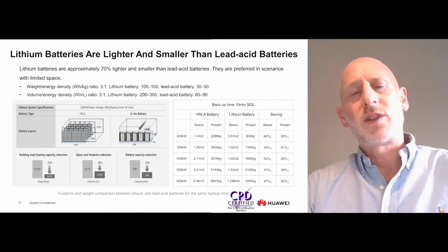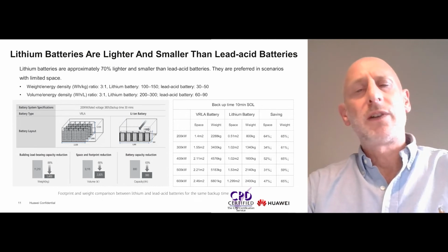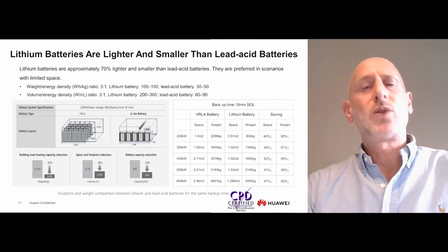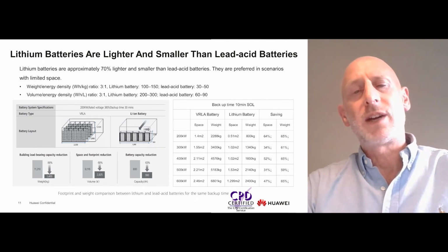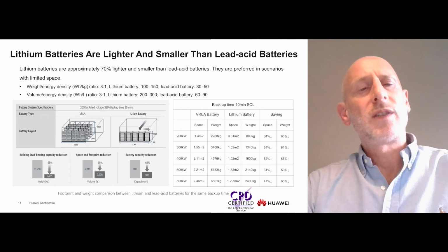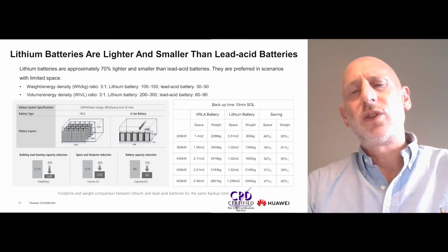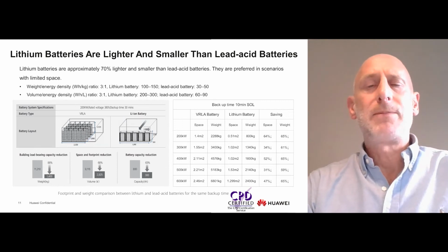According to research results in different scenarios, in the 500 kilowatt 10-minute scenario, the lead-acid area is 2.21 square meters with a total weight of over 5,000 kilograms. The lithium battery area is 1.53 square meters with a total weight of just over 2,000 kilograms. The space and weight of the lithium batteries are reduced by 31% and 59% respectively.